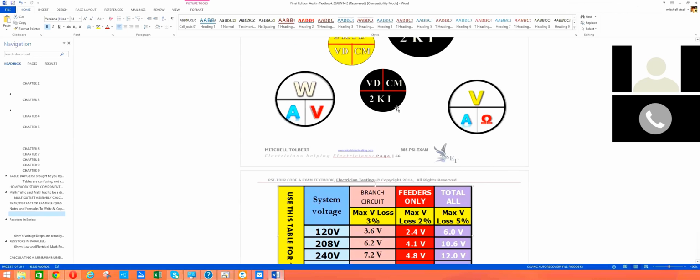Okay. So that's what I'm going to plug in right up here for this voltage drop. I'm going to come up here and put in that actual value that I'm looking for as far as a fixed-in-place value, so 6.24 volts. That caps my losses there, so to speak, and that's going to give me that little quadrant.